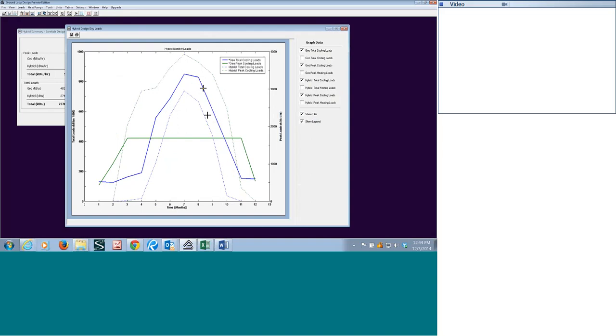And you can see that's a pretty good chunk of heat rejection. The solid green line is our peaks, and that's what we shaved on this. By shaving those peaks, you'll also notice the hybrid total cooling loads, which, I can't make out that color, guys, I'm sorry, I believe is this line right here. It's blue dashed. Okay, so that would be this line. And then we have our hybrid peak cooling loads, which is this dashed green line.